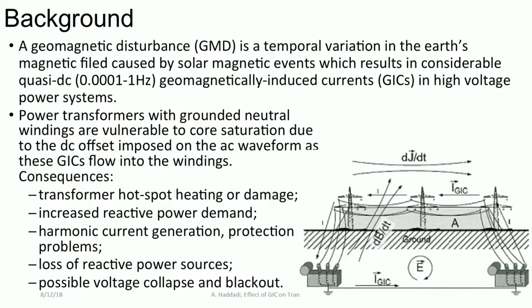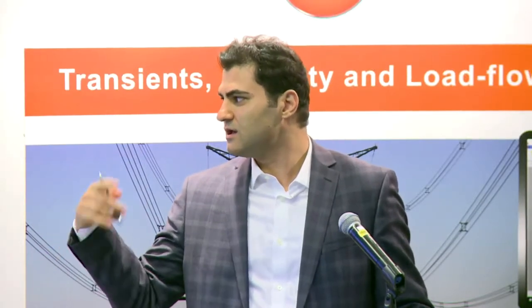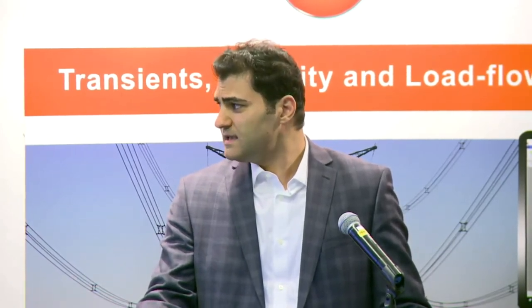These electrojet currents induce a varying magnetic field — shown in this figure as dB/dt. This varying magnetic field induces a varying potential on Earth's surface, shown here as E. The potential results in quasi-DC current circulating into the transformers and into the transmission lines. The main impact of these currents in power systems is transformer saturation, which is the main cause of problems in a geomagnetic disturbance.